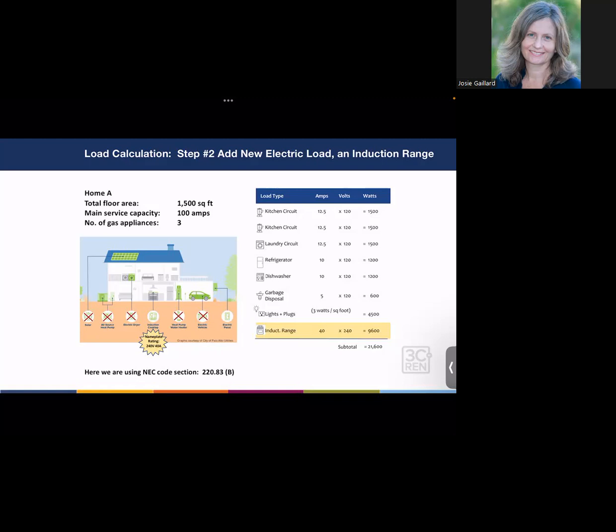So that's all the appliances and loads in the home as it was before the induction range, shown in white on the right. Now we add the induction range in yellow. Because there's a nameplate on the range, or a data sheet we got before buying it, we know it's rated for 40 amps at 240 volts, for a total of 9,600 watts. So that subtotal comes to 21,600 watts.